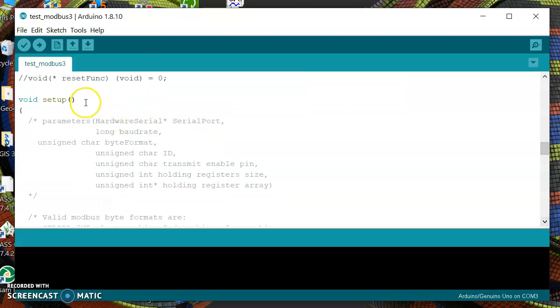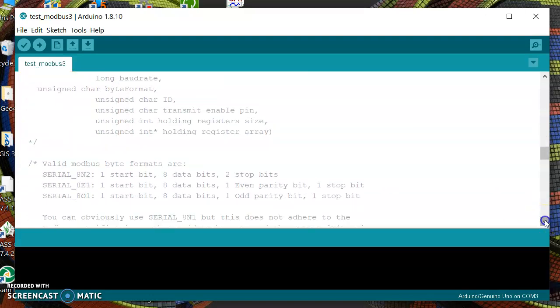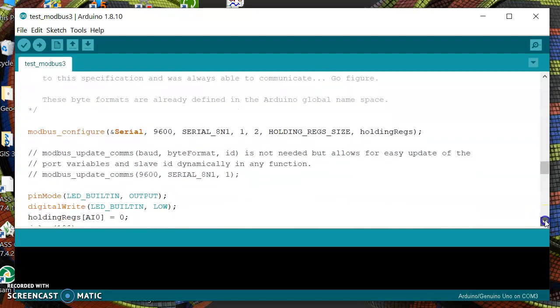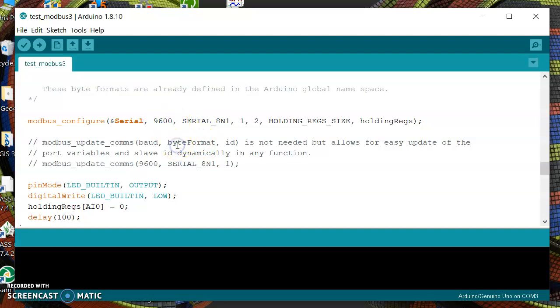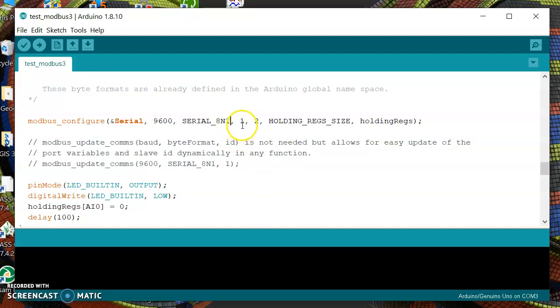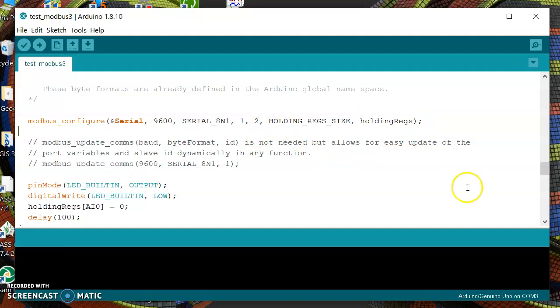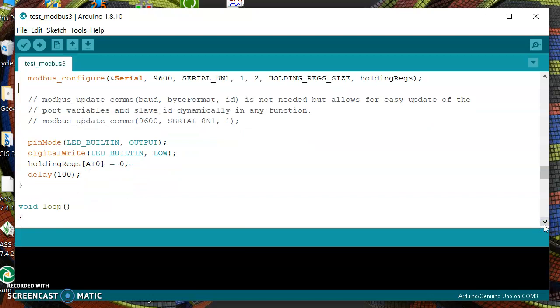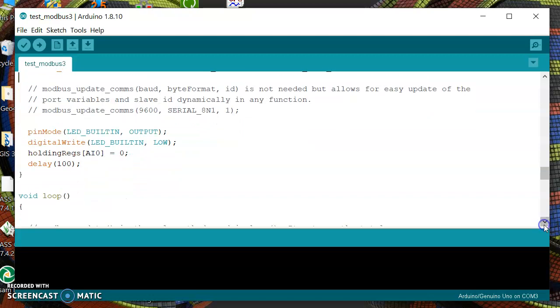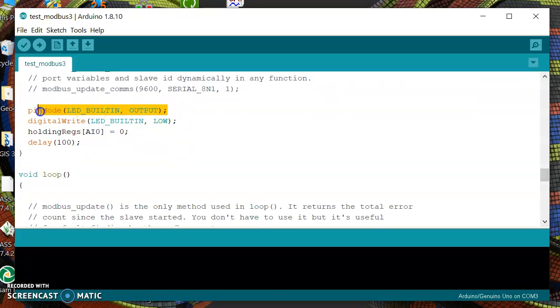In setup it's very easy. We are going to use this function modbus_configure serial port 9600, this is the bits per second rate, and then the format will be 8 bits of data, no parity, and one stop bit. Then we have the address, the size, and the register where we are going to record this data.